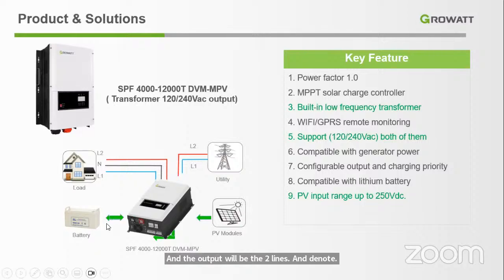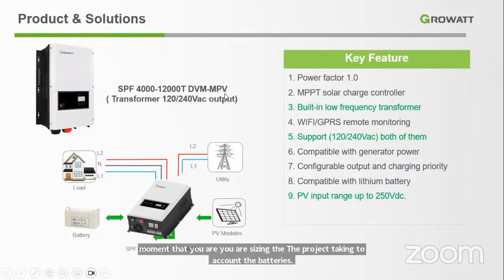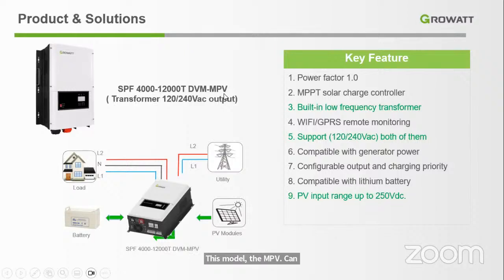Please consider connecting the battery and the PV modules to work at 100%. This doesn't work without a battery, so when you are sizing the project, take the batteries into account. This model, the MPV, can have 250 volts DC, so you can have more panels to supply the loads.